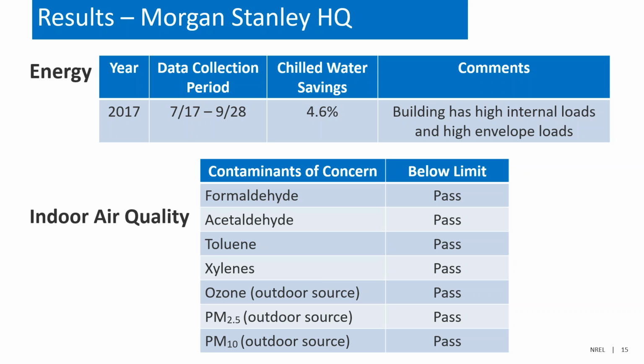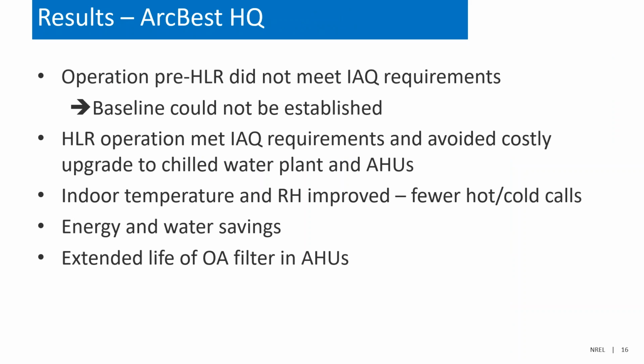So reducing the outdoor air can actually improve the indoor air quality from those sources. And that's true of other locations with poor outdoor air quality. This technology can help significantly. All right, the ArcBest headquarters, as I said, they were over occupied in the building compared to the design. So we couldn't establish a baseline because we couldn't meet the ventilation and IAQ requirements with the existing system.